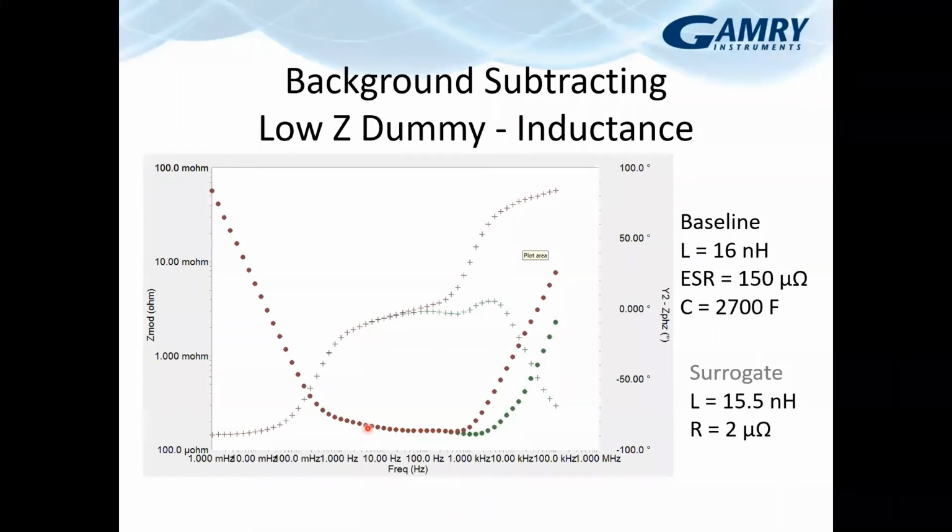It's a lot better for any measurement where you have a known value and another known value. A good example of that is if you have a full cell and a 3-electrode cell, you can measure the full cell, you can measure the 3-electrode cell, and then you can subtract the 3-electrode measurement from the 2-electrode measurement to get the impedance on the second electrode.